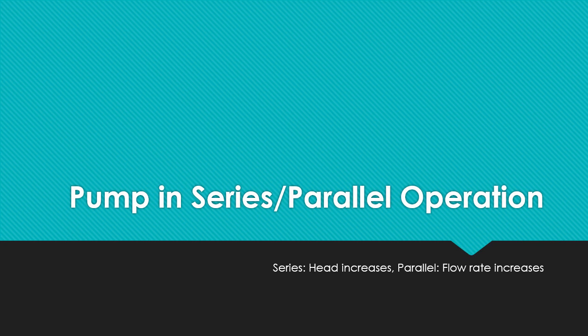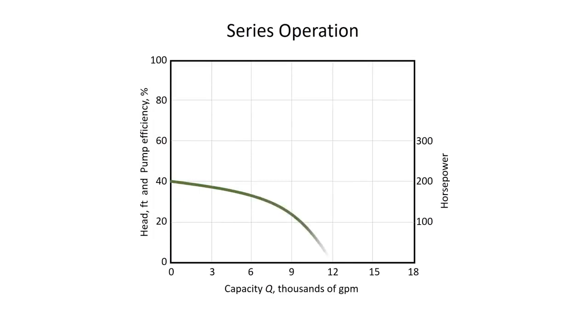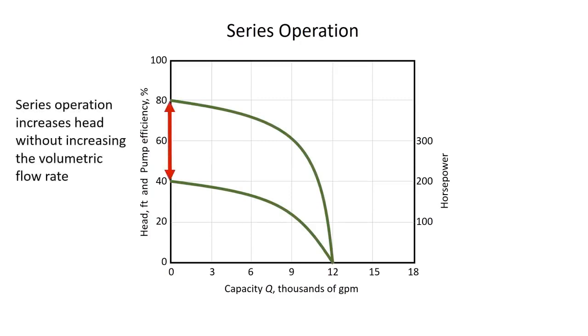What will happen if we add two pumps in series and what will happen if we add two pumps in parallel? If we add two pumps in series, the head increases. Whereas when we connect two pumps in parallel, the flow rate increases and the head remains the same. In series operation, one pump discharges into the suction of another, resulting in an increase in head but no increase in flow rate.